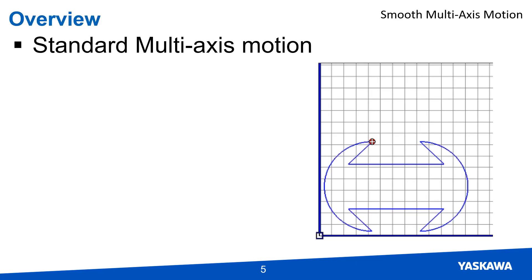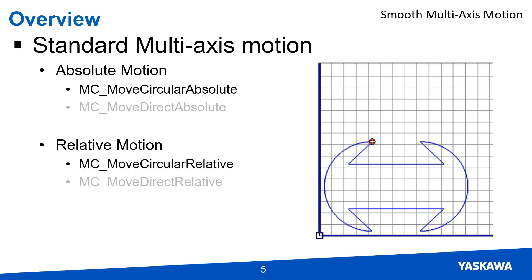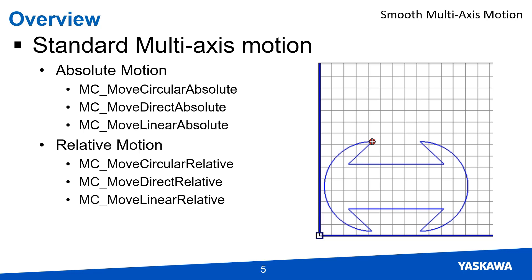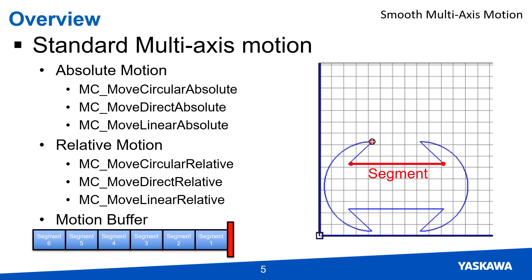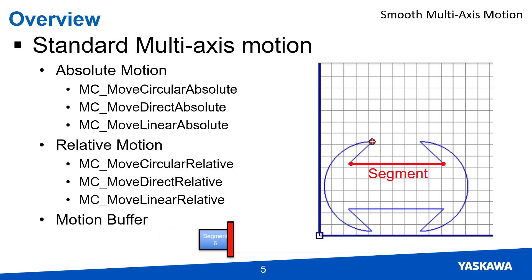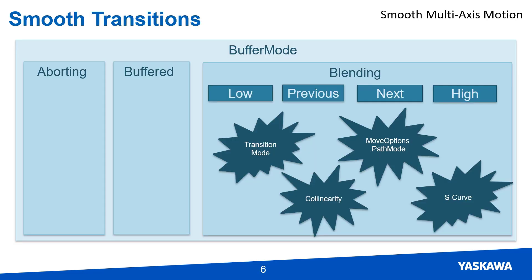To talk about smooth motion, we first have to review how normal multi-axis coordinated motion is created. Just like a single axis mechanism, there are relative and absolute moves that can be used to move the mechanism. For multi-axis coordinated systems, there are three types of moves: circular, direct, and linear moves. Each move from point to point is considered a segment. When a motion function block executes, that motion segment is added to the buffer and moves through it until the controller processes it and moves the actual motors. How these segments are joined determines visually and mechanically how the mechanism is going to perform.